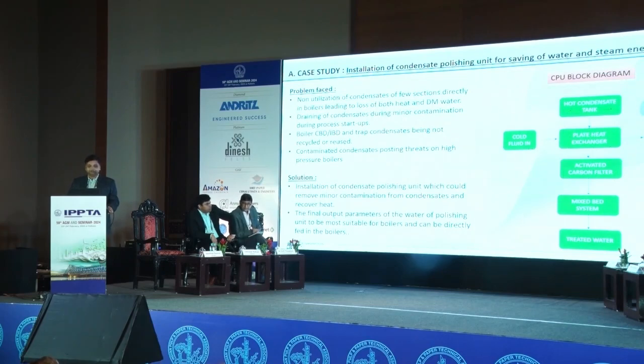The solution we identified was to install a condensate polishing unit, which will polish the condensate to the quality of boiler water and recover heat as well. The final output water from the polishing unit will have parameters suitable for direct feed to the boilers. This is the block diagram of the polishing unit.